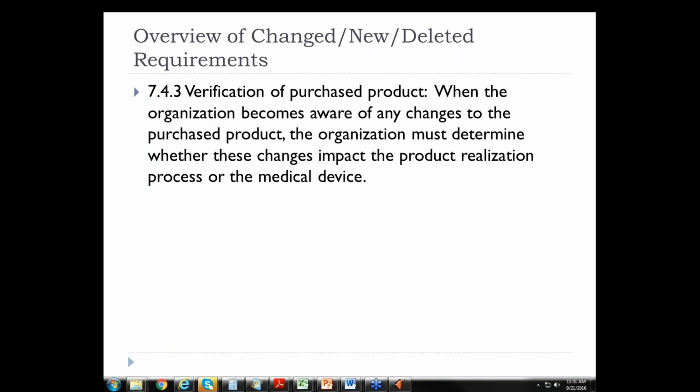What if a company, I get this question a lot, what if a company manufactures parts for medical devices, not the medical devices themselves? Can exceptions be taken? Exceptions can be taken, Fred, but again, they have to be justified, and those justifications will be evaluated by the auditor.